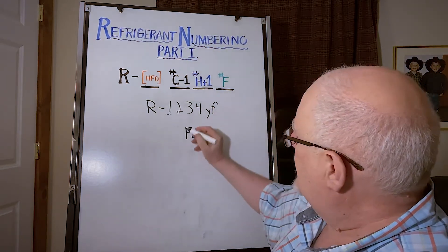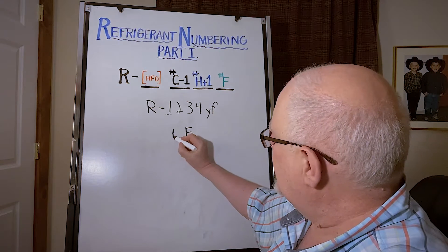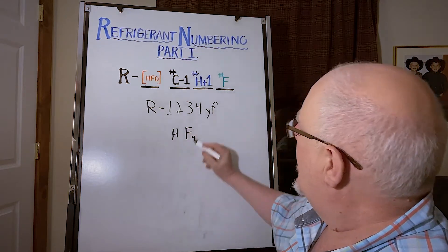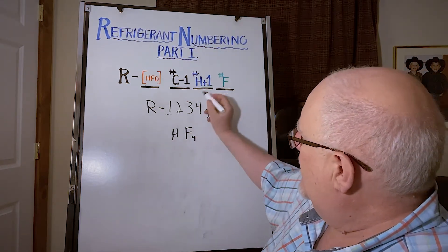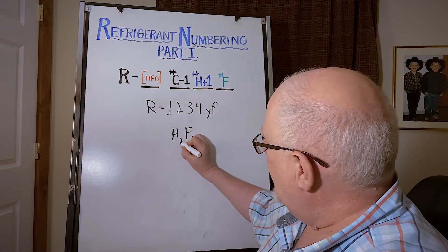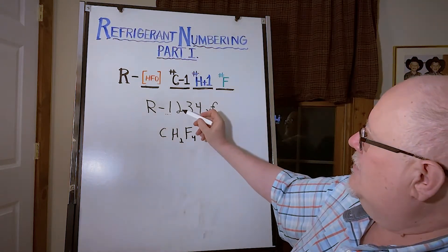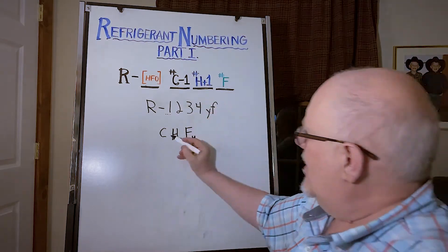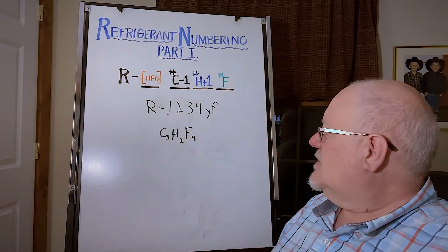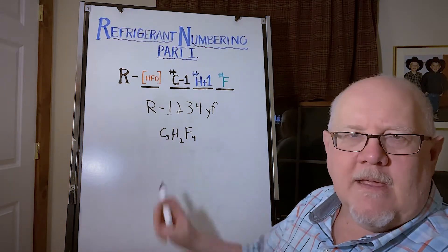We know it's an HFO because it has a one out here from that digit. But working from right to left, we have four fluorines, and the number of hydrogens is going to be three minus one, so it's going to be two hydrogens. Carbons, we have a two, we know that's one less than the actual number which will be C3. So we have tetrafluoropropene.